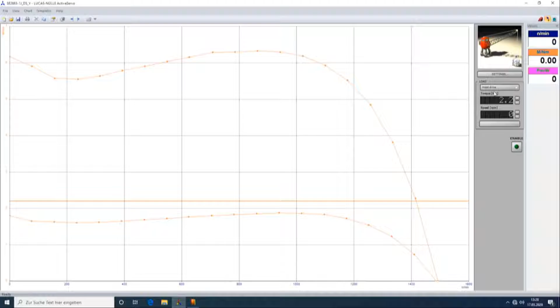the Y circuit or star circuit, and nothing happens. The motor couldn't start. There's not enough torque to start. We see here the working point is at this point, and no turning of the motor. If I go to delta, I see, okay, the motor is turning. So for this special machine, star-delta is not working. But what is happening with the current inside the system?